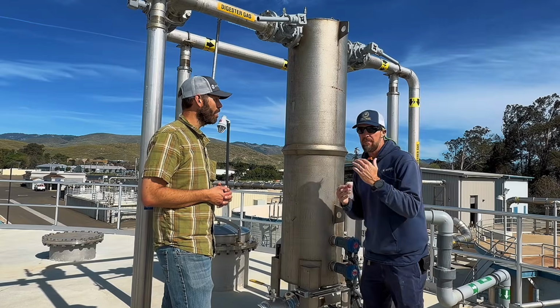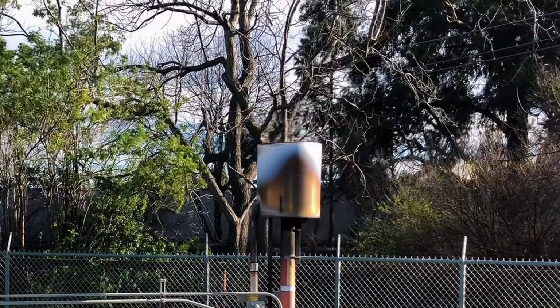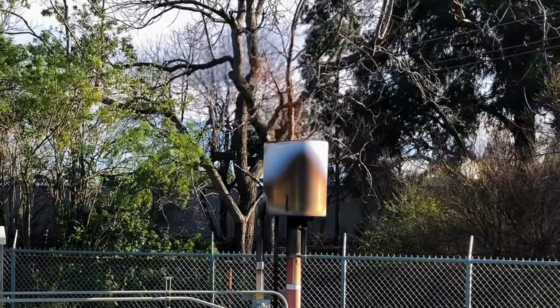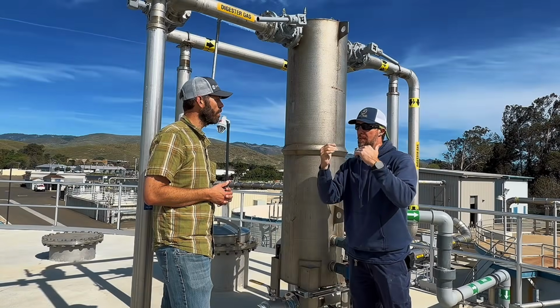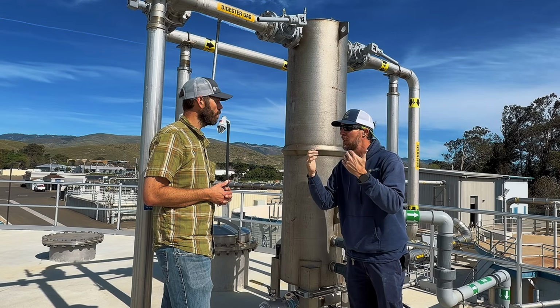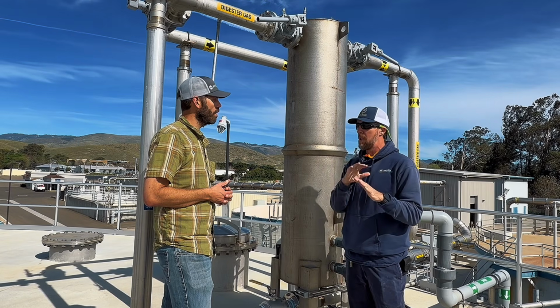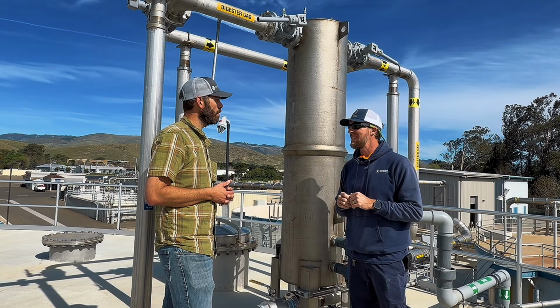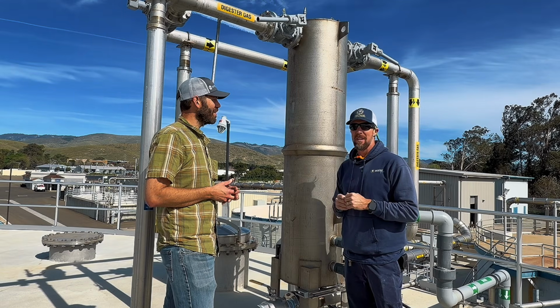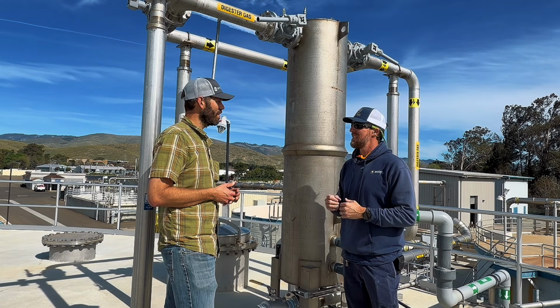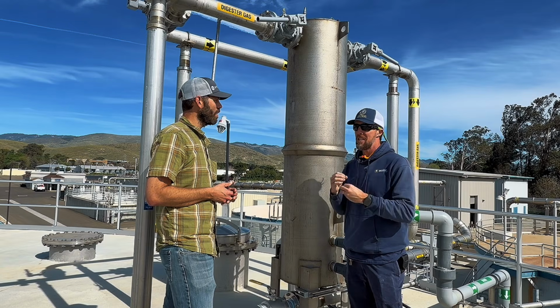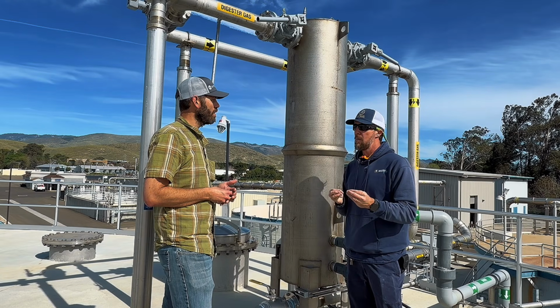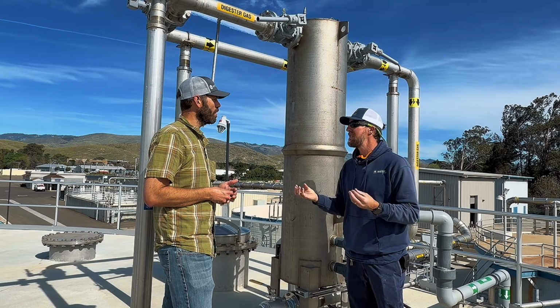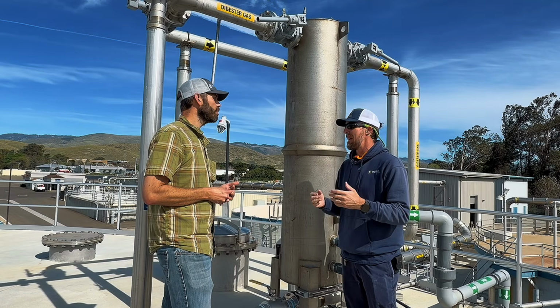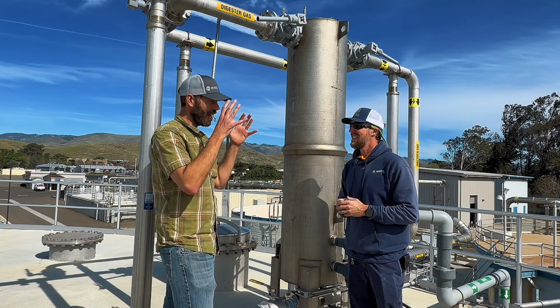You don't want to put too much to the flare. Your flare is huge. You don't want to pull too much to the cogen, or your flare is going to go out. So find that balance to sustain the flare, because sometimes it's a little overly windy, too much wind, a little blowout. Don't want to see that. Yeah, doesn't happen very often, because we have the set points over years dialed in to a spot where the cogen can produce as much as it can, but we ensure that we uphold our APCD permit, Air Pollution Control District permit. Absolutely.